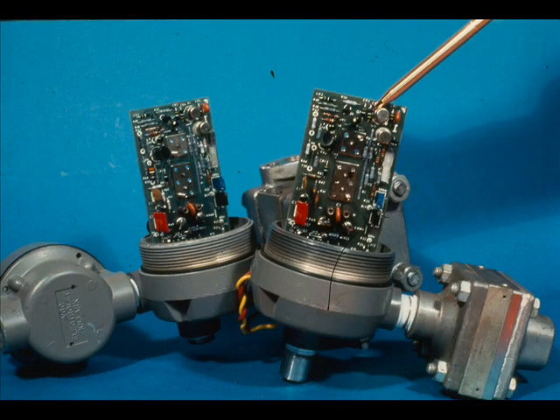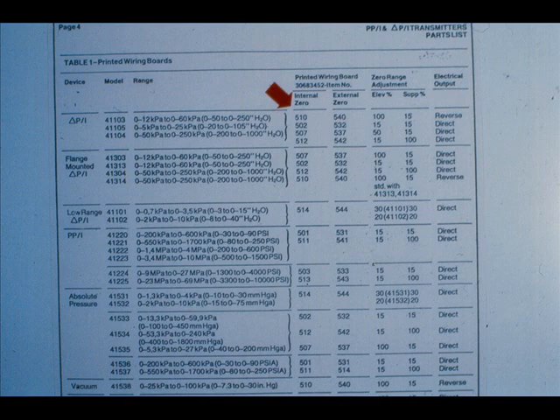The circuit boards are basically the same. They differ in the percent of suppression and elevation possible, the amount of coarse zero adjustments, and the range of the transmitter. Even though the circuit boards are basically the same, they are not interchangeable.